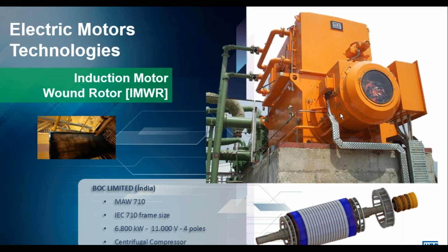With that in mind, it's common practice historically, slip ring motors would be supplied with fixed brushes only, regardless of whether they were being used for speed variation or not. It is now common practice to install a brush lifting device so that after starting, the rotor gets short-circuited and the brushes are able to be lifted, avoiding a lot of this problem of dust buildup.